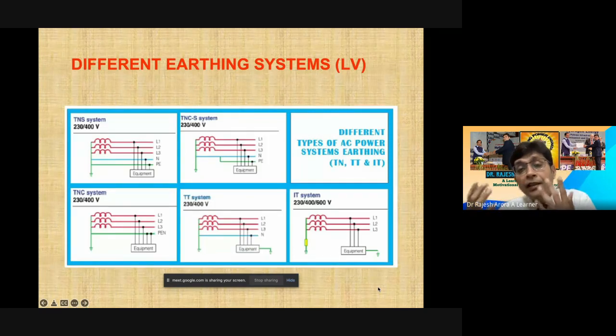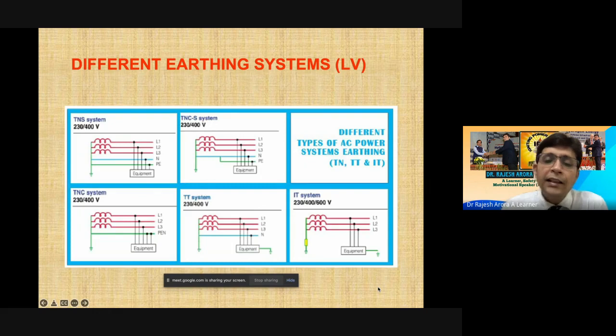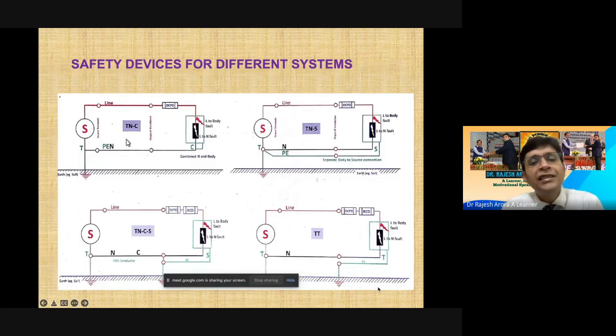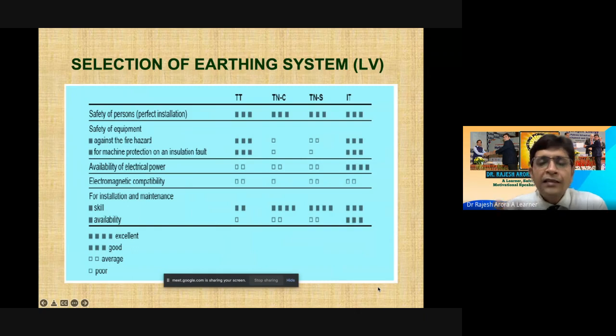You have to understand different earthing in LV systems: TNS system, TNCS system, TNC system, TT system, IT systems. Based on your requirement, you have to select protective devices associated with all these systems. Where you need OCPD, where you need OCPD with RCD. You have to be very much careful. These are the comparisons of all systems of earthing we usually come across in LV systems: TT, TNC, TNS, IT.